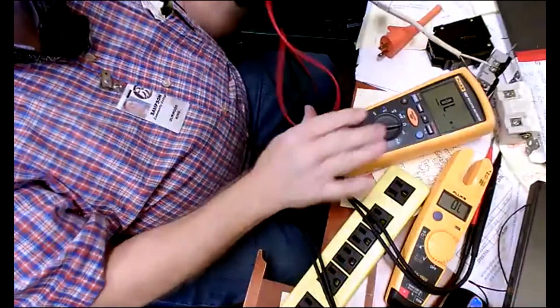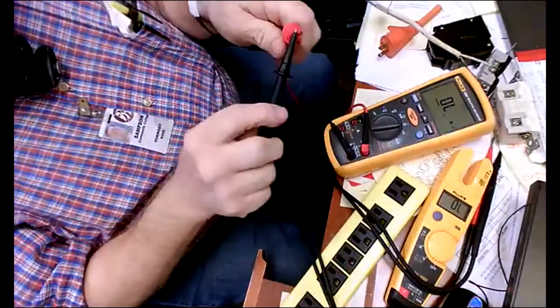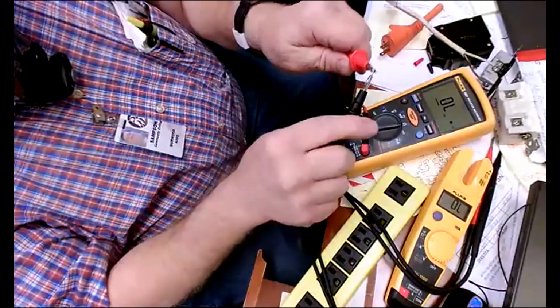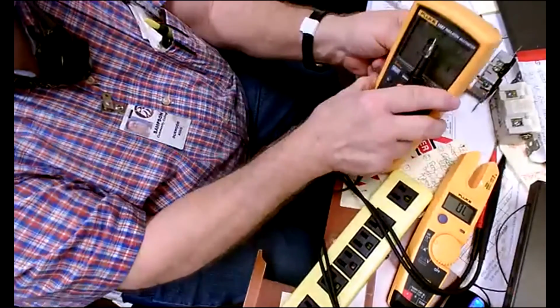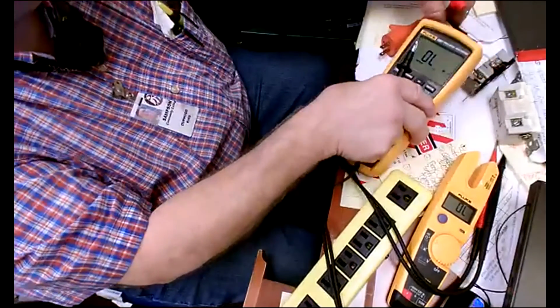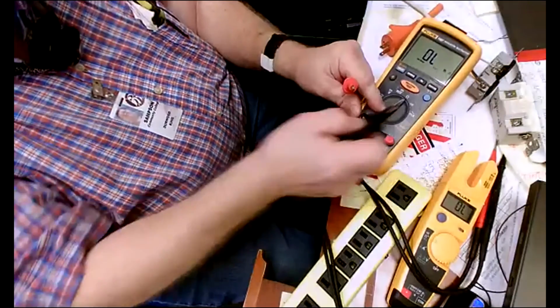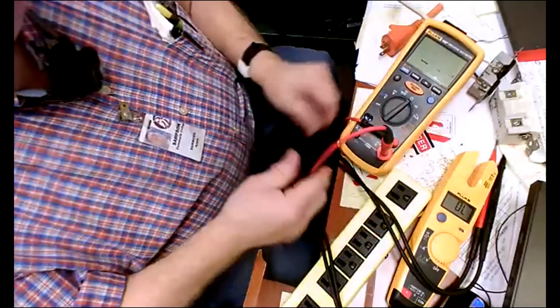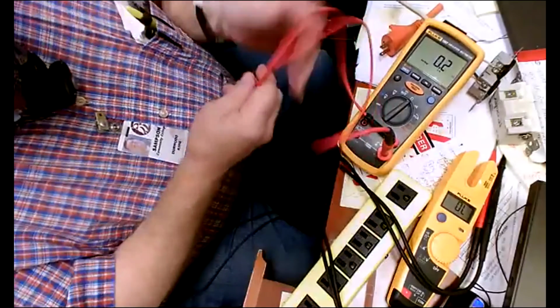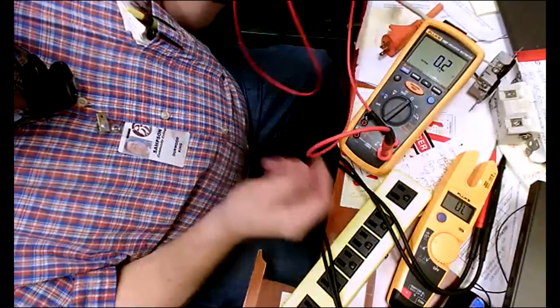Yeah. And what you can do as a diagnostic would be this. Let's say this meter here has detachable leads. If you put them together and it said, say, 20 ohms, when it says 0.3 right now, then you pull out the black lead, and you can take the red one, and if you can make contact down in there, let the red lead go in and out and see, is the red lead the problem? And that red lead's fine at 0.2 ohms.